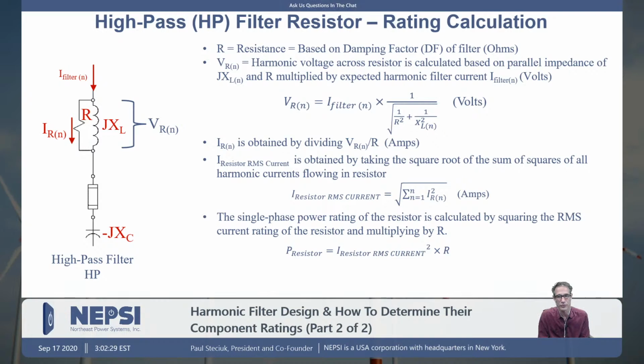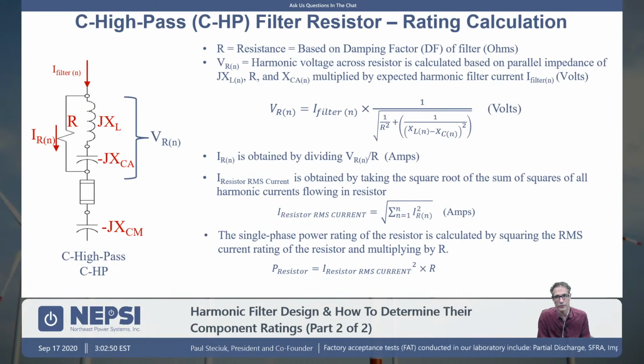And this is the process. The resistor supplier wants to know what's the system voltage and what is the kW losses within the resistor. So the resistor is being based upon ohms, the voltage rating, and the watts. What is the watts? And you want to be conservative when you're picking your resistor. Perhaps double the rating of what you would expect, so that you have a lot of margin in your design.